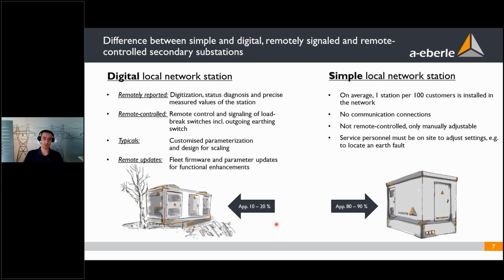The key features of the digital local network stations are that they are remotely reported. This means that all the measurement values and the status diagnosis is digitized inside the station, and then your control center receives precise measured values of the station. Also, these stations are or should be remote controlled. This means that you can remote control and signal your load breaking switch, including the outgoing earthing switch. And that way you can have remote switching operations and control which feeders are connected to which substations.